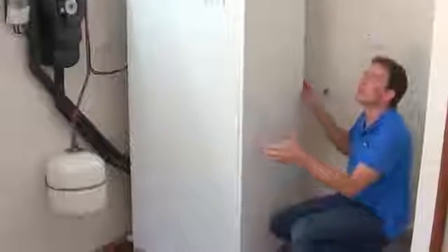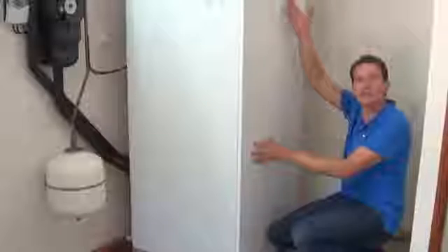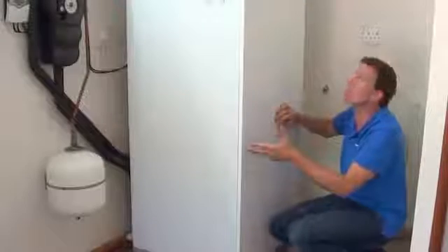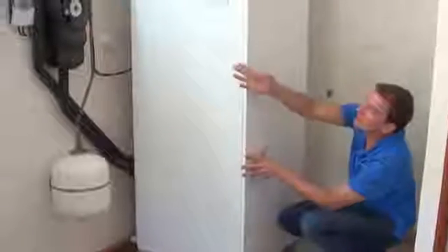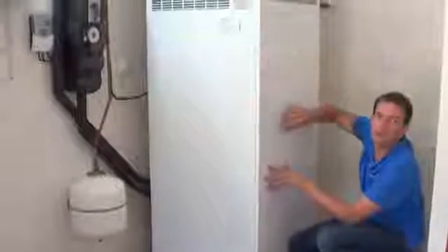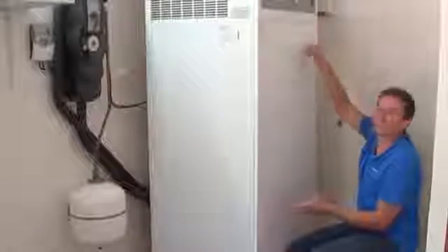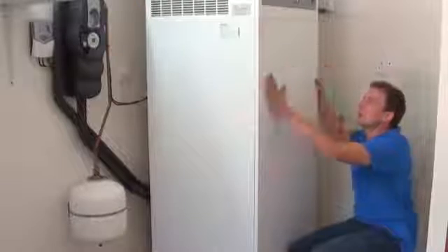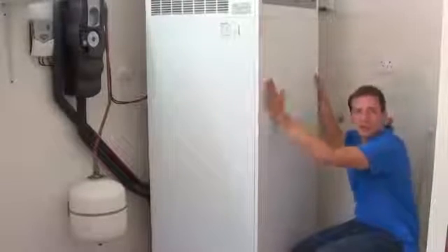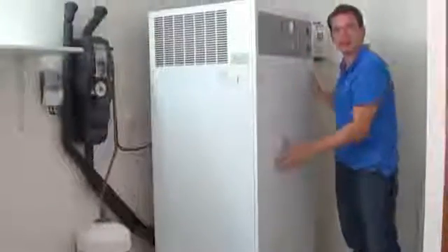You will never have maintenance because you never have to circulate water to a heat pump and back. There are no circulation pumps that transfer the water to the heat pump and back as in normal conventional heat pump systems. Which means it's less maintenance, and it also consumes less energy from the grid because you don't have any circulation pumps. Also, if you keep them insulated in one unit, you also have less heat losses between the heat pump and the tank.